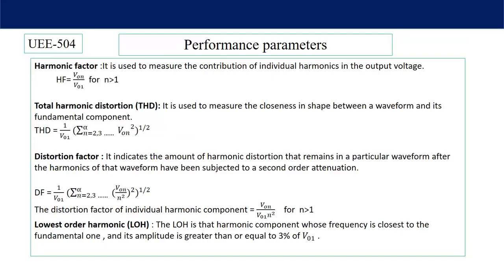Performance parameters of inverters. The quality of the output voltage and output current — these parameters are very important. Harmonic factor is used to measure the contribution of individual harmonics in the output voltage, that means how much amount of third harmonic, fifth harmonic, or any other harmonic is present. The harmonic factor equals V_0N divided by V_01, where V_0N is the RMS output voltage of the Nth harmonic and V_01 is the RMS output voltage of the fundamental harmonic, for N greater than 1.